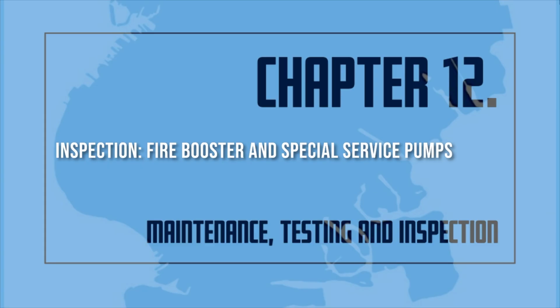Electrical system. A visual inspection shall be performed weekly to ensure that the controller pilot light is on, the transfer switch is closed, the reverse phase alarm pilot light is off or on normal phase rotation, the pilot light is on, and that the oil level in the vertical motor sight glass is normal. Circuit breakers or fuses are to be checked monthly, and any potential wire chafing, where wire is subject to movement, shall be checked quarterly.